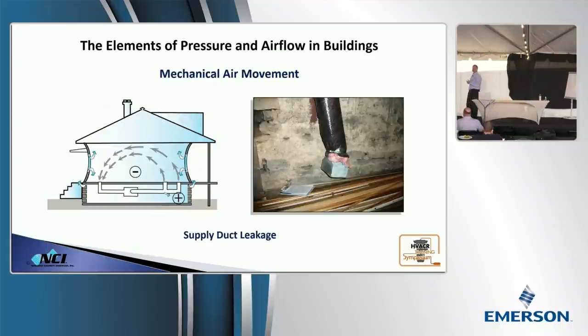What about mechanical influences? You start to put a fan behind these things. That's just Mother Nature controlling it in the previous slides. Now we're actually putting fans behind this, up to 4 times more of an influence than Mother Nature, and they're consistent. Supply duct leakage: if you've got combustion equipment located inside the conditioned space and you have supply duct leakage to the unconditioned space, you're pulling that space into a vacuum. And it's trying to get air from wherever it can get it.